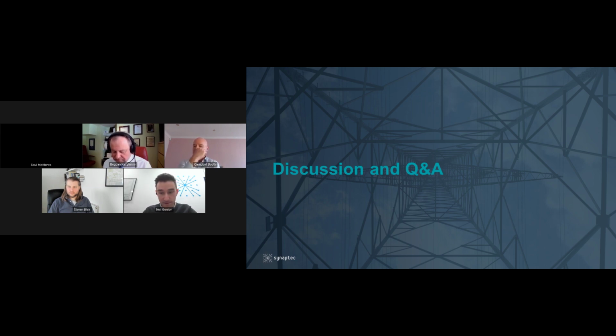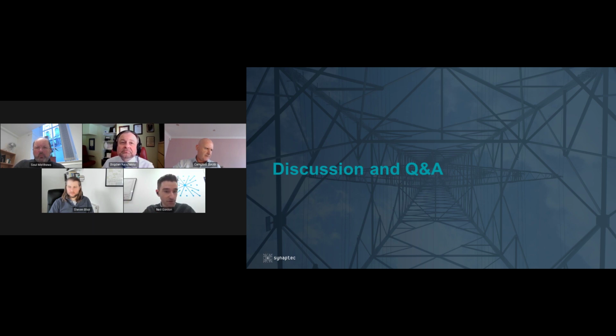They all look the same to the interrogator. And it's about how we calibrate those sensors at our facilities and the algorithm we deploy on the interrogator to convert each of those wavelengths into the parameter that's actually being measured at that location. That you mentioned, Saul. So that's an important thing to touch upon because we multiplex all of our sensors along a single mode fiber by wavelength, and because the speed of light in the fiber is a very well characterized, well-known quantity, that means for every sensor, and most importantly for the electrical sensors where you need those to be properly synchronized to GPS, we can kind of align those measurements sample by sample back at the interrogator, because we know the time of flight in the fiber and we can correct for that actively. So it means that you bring all those sensor measurements into global alignment back at the interrogator with GPS time without having to do any kind of clever calibration. You just need to know the distance in the fiber to do that.